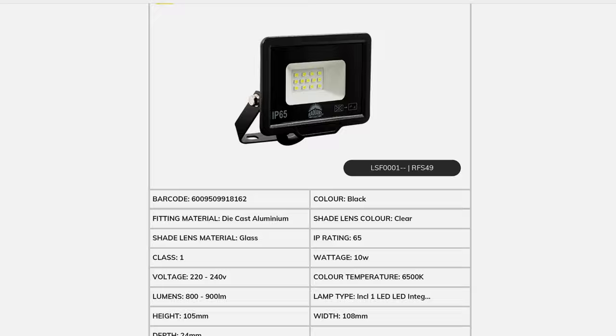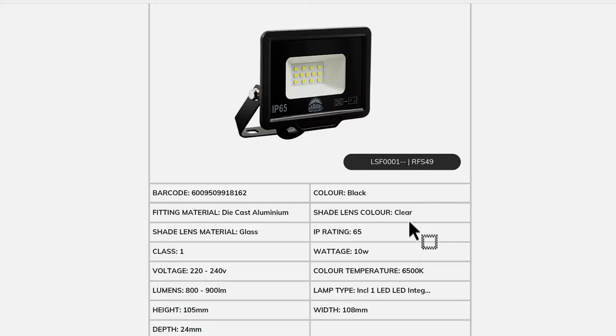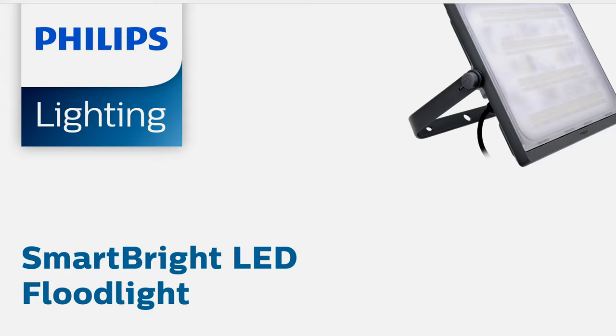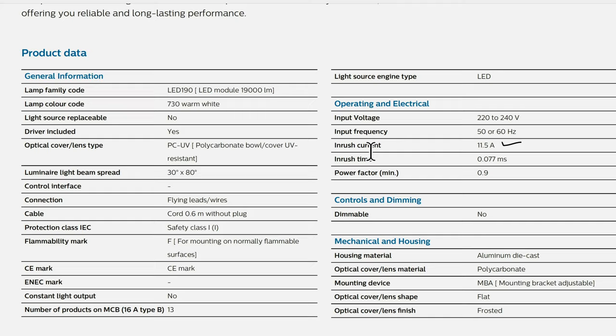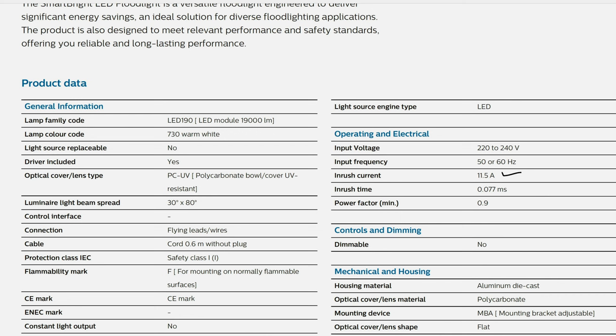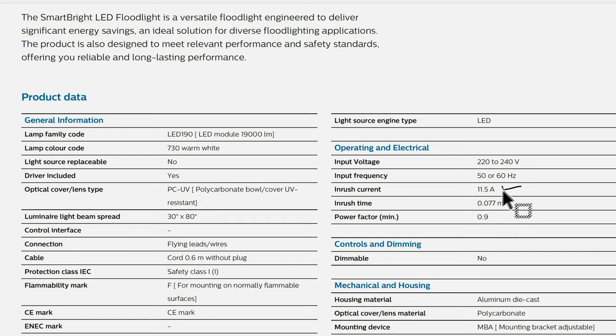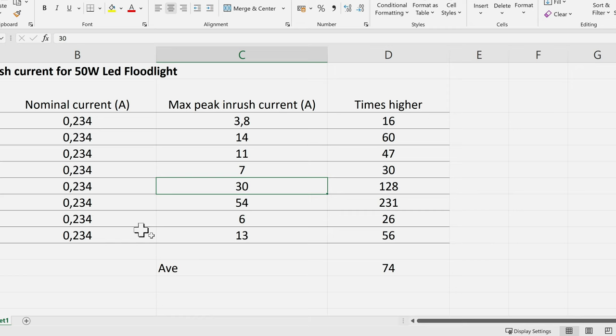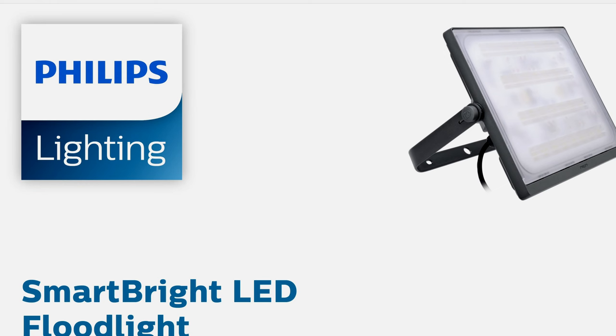Some product sheets provide very limited values, so one can't do much without measuring the inrush current oneself. However, the SmartBright LED floodlight datasheet does give the inrush current. Keeping in mind this is a 200-watt floodlight, the inrush current listed is only 11.5 amps — much lower than what I measured for a 50-watt floodlight. The reason is the driver circuit: more premium floodlights may be designed to lower inrush current, using a soft start or an inductor in the circuit to reduce it.